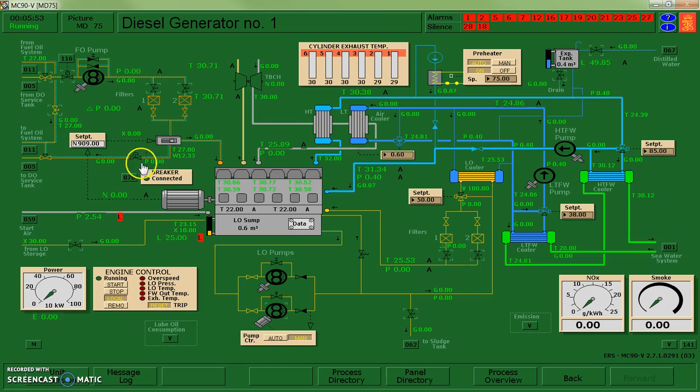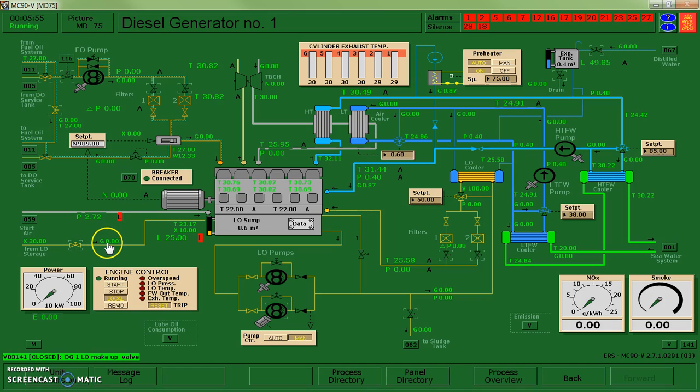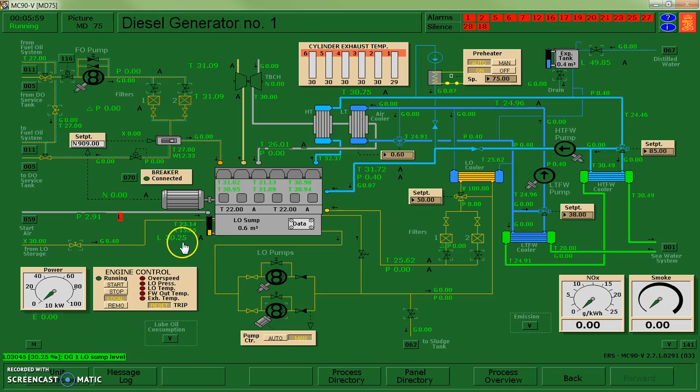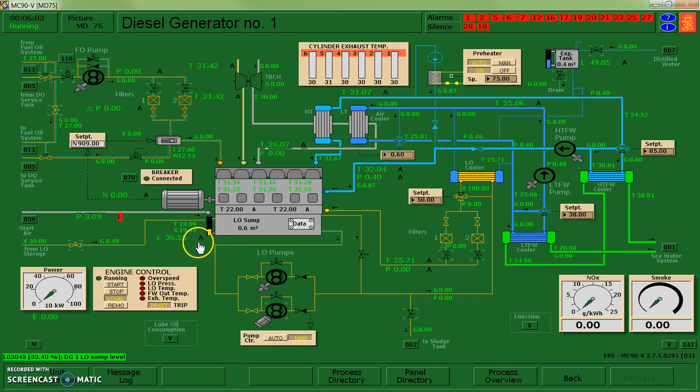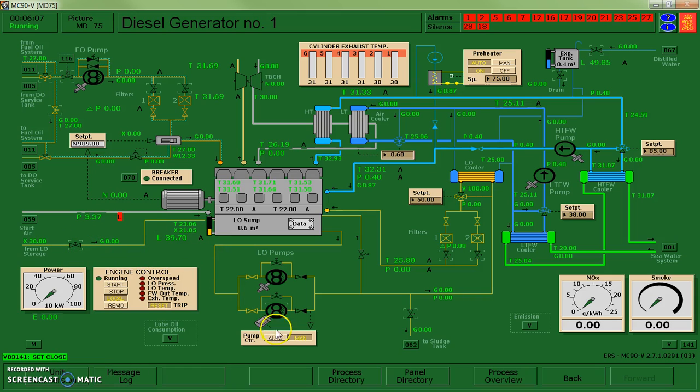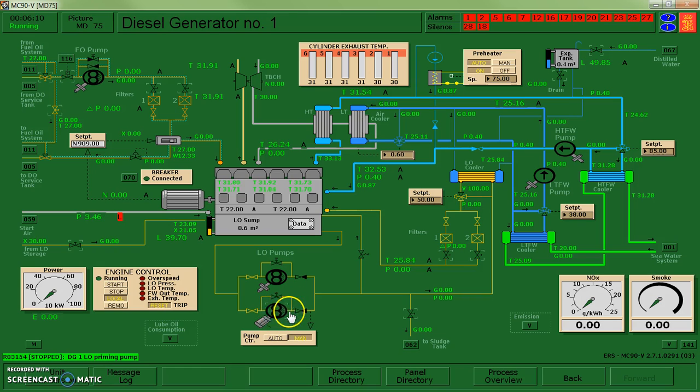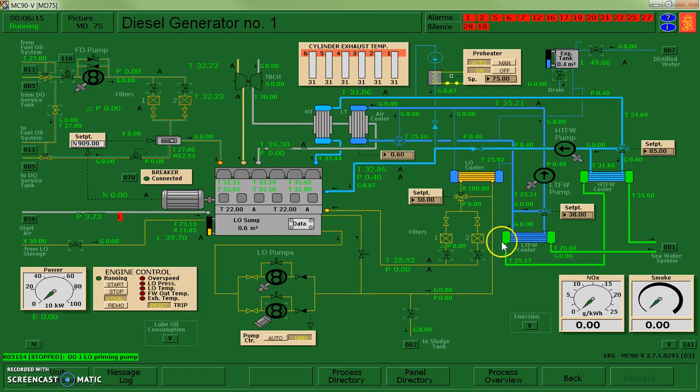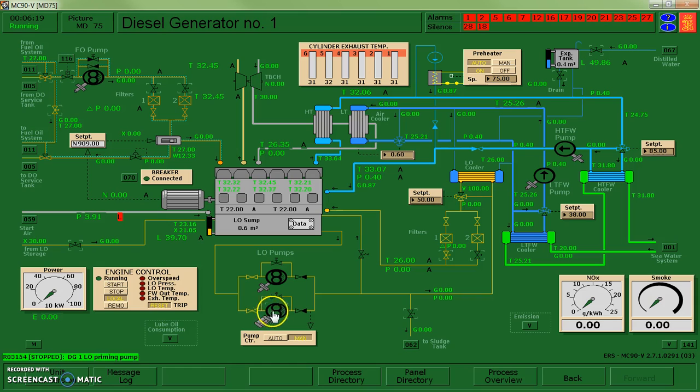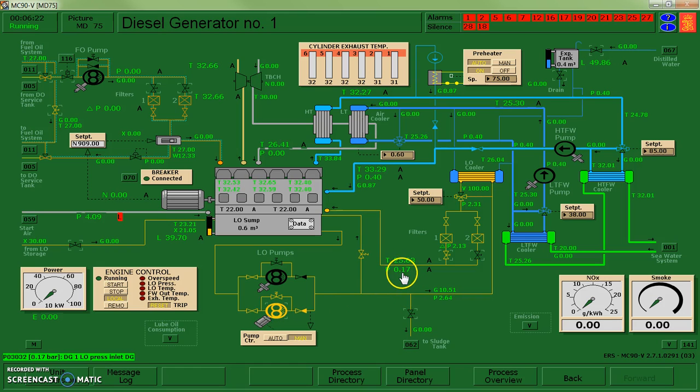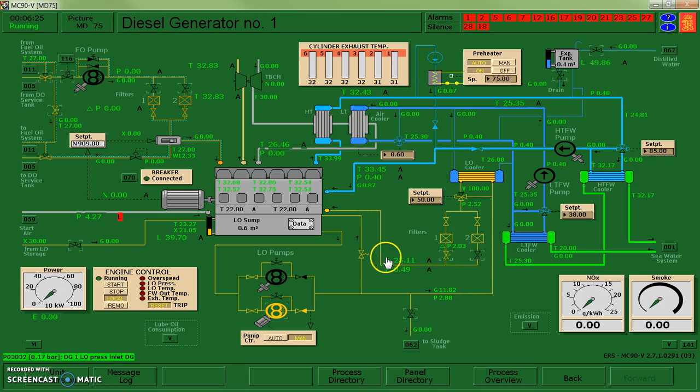So let's start with the lube oil. First thing I want to do is add in some lube oil so that I'm out of the danger zone for low oil. I have my manual lube oil pump active. And I'm going to turn that on. First what I want to do is open up one valve so that I have a pathway in. So if I turn that on, what I should see is my pressure and flow starting. So I'm starting to circulate some of this oil.